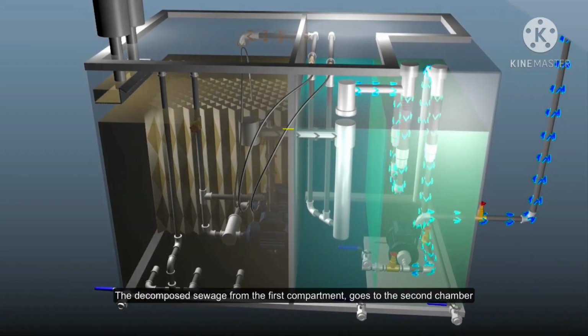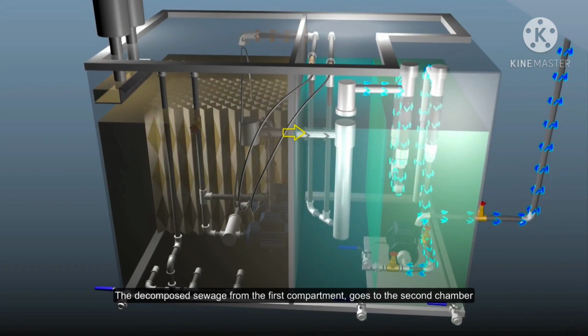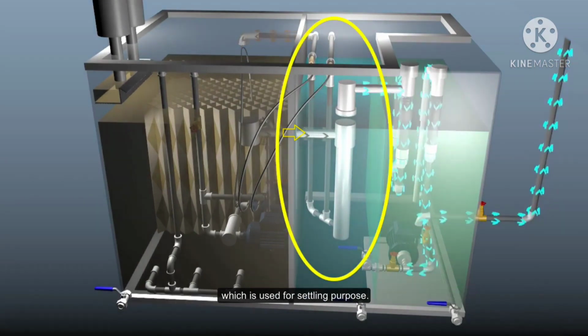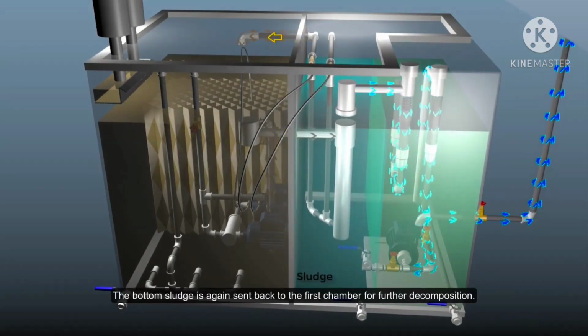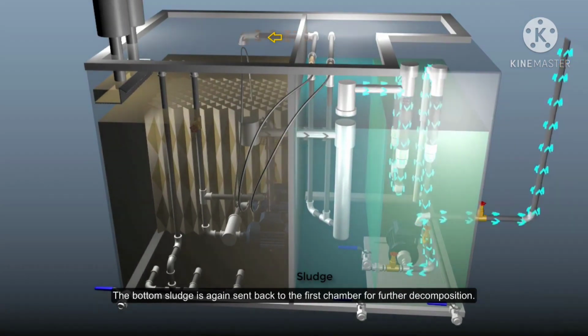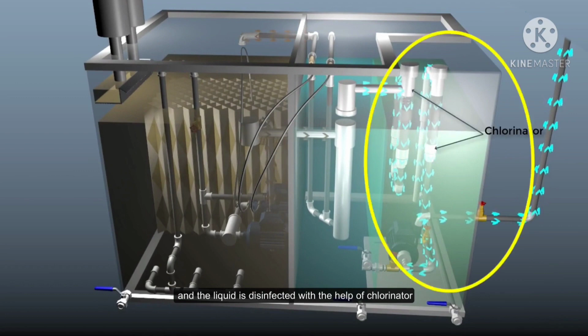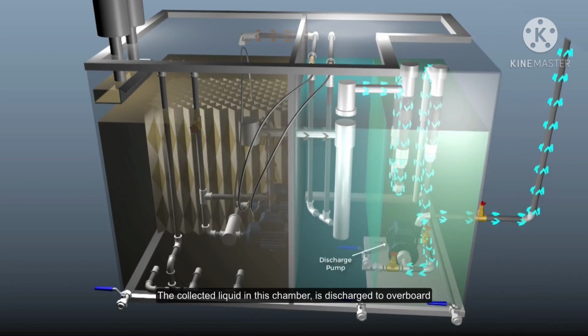Then, the decomposed sewage from the first compartment goes to the second chamber to separate the sludge and clear liquids by settling. The sludge is sent back to the first chamber for further decomposition. However, the separated liquids overflow to the third chamber, passing through the chlorinator in order to disinfect. Now, the collected liquids in the third chamber can be discharged at sea.